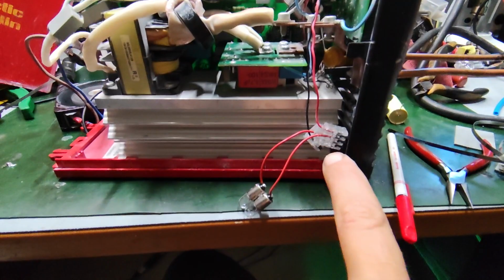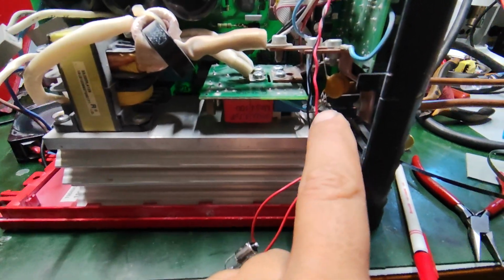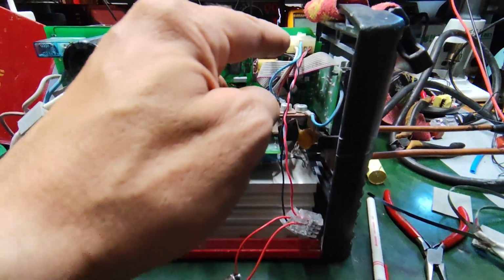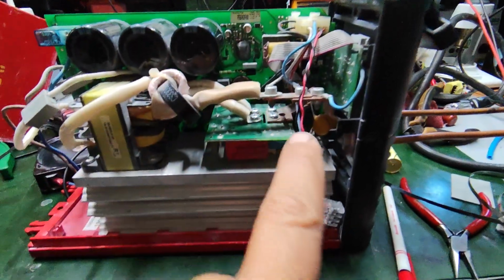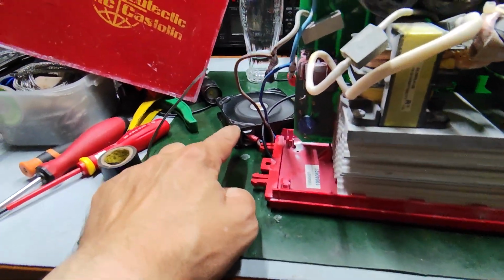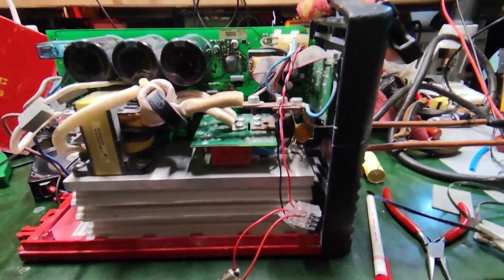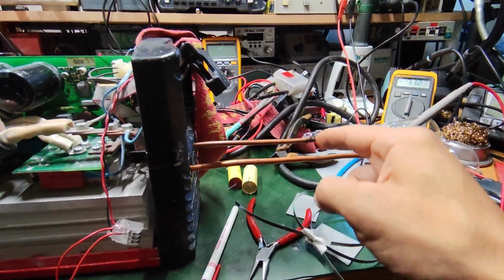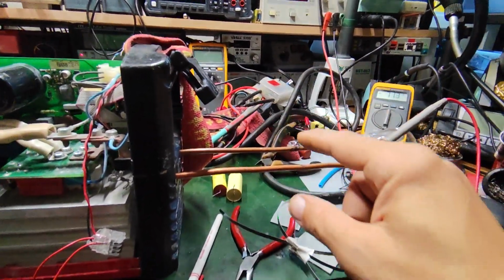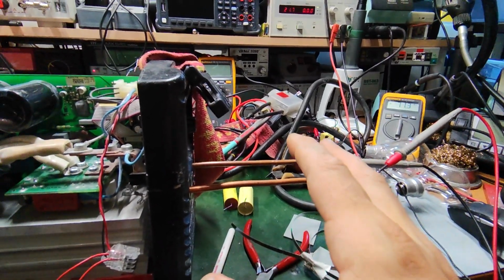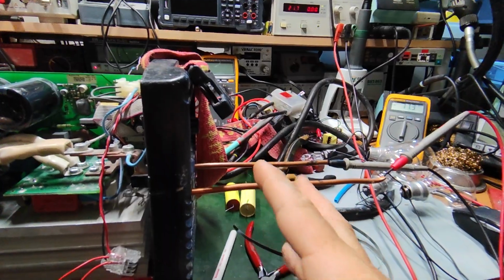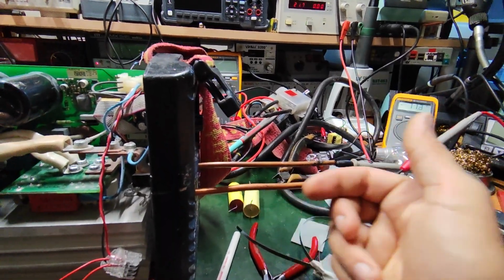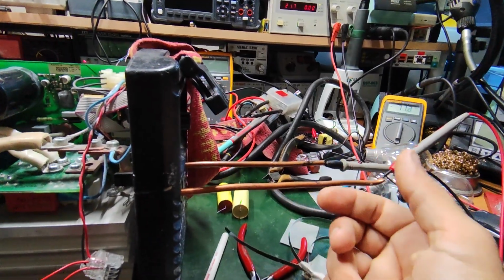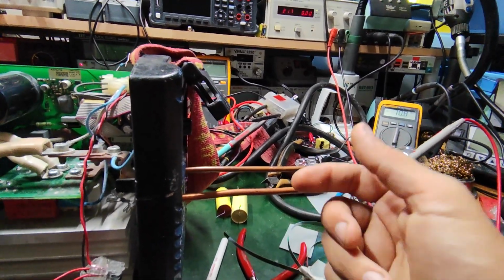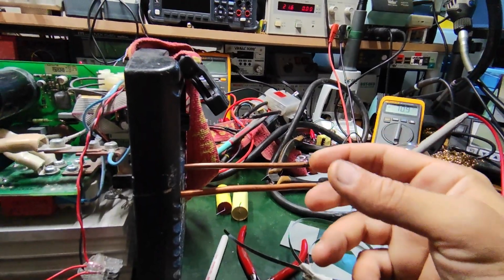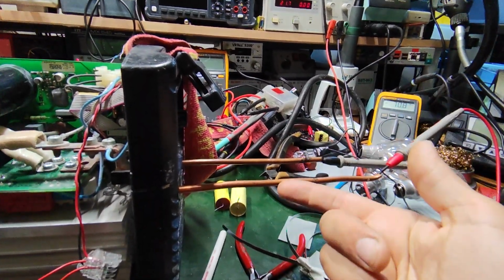Further, I will put a little relay here, constantly connected, and this relay will command this fan. But for this, I need to have the cable and test it, because the cable is mainly responsible for this issue. There is probably a very bad connection, or maybe the cable is broken underneath the plastic, and maybe it causes this issue.